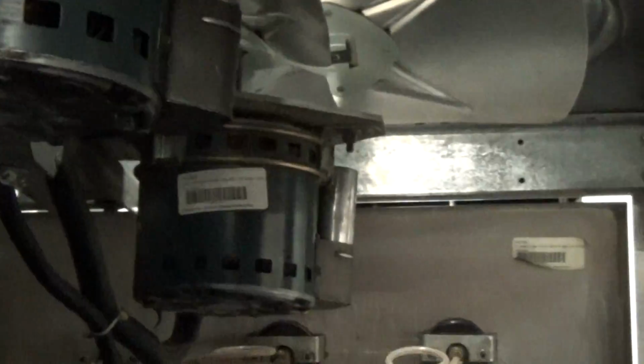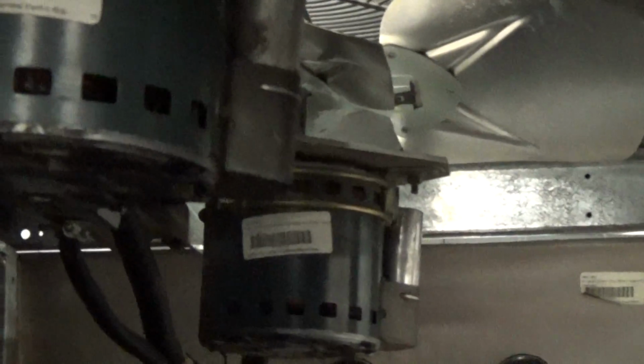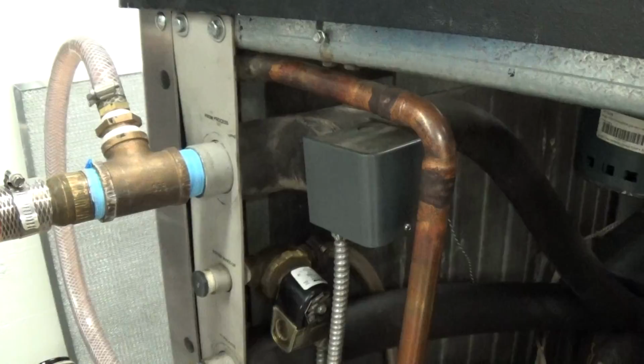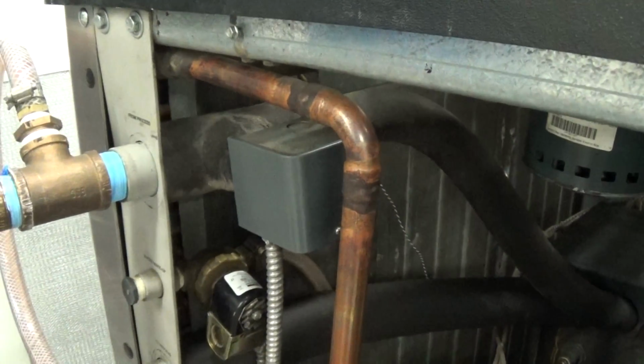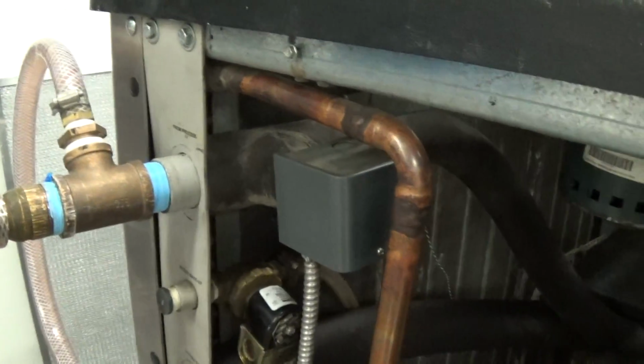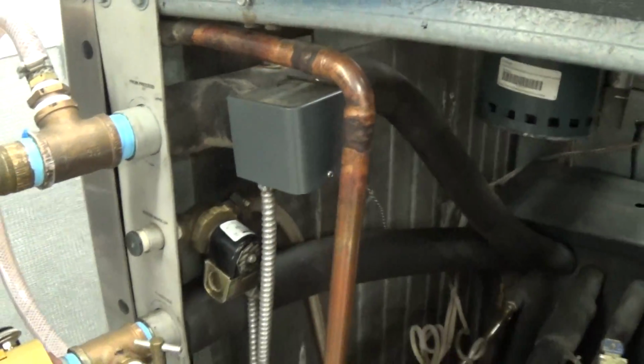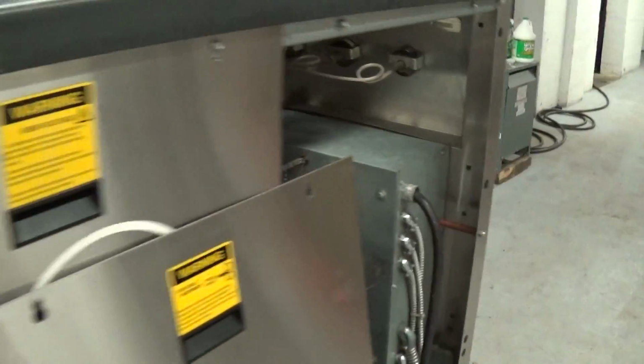And we have our dual fans for the chiller up top here. And here we have a flow switch, so another nice redundant feature. The chiller will go into alarm and shut down if it does not have appropriate flow. We'll go over some other things after we get the unit going here. So we're going to come over, give us our main power.